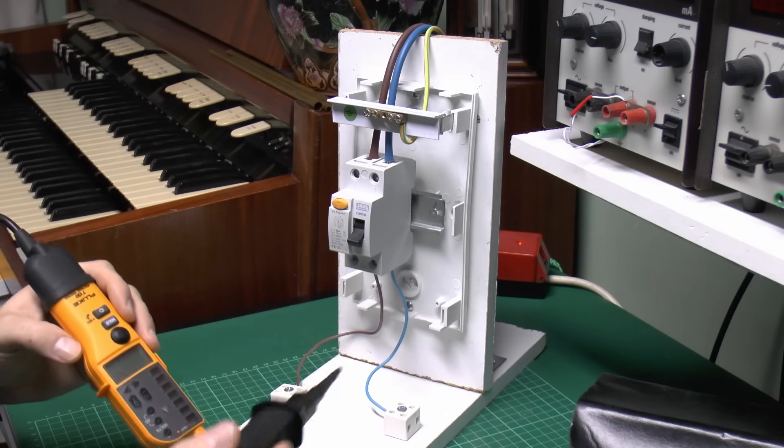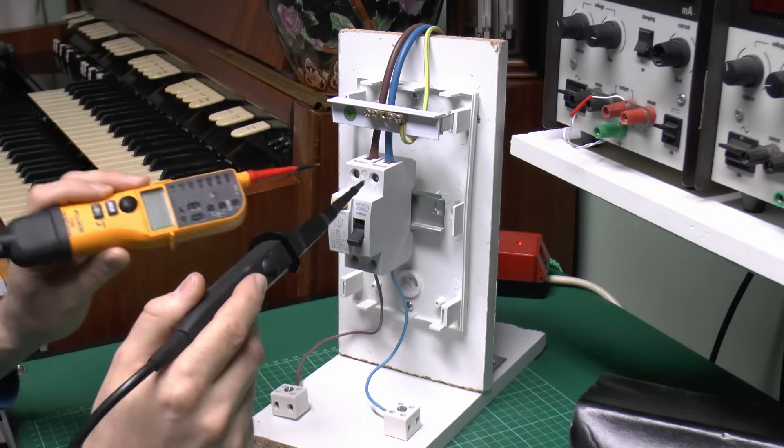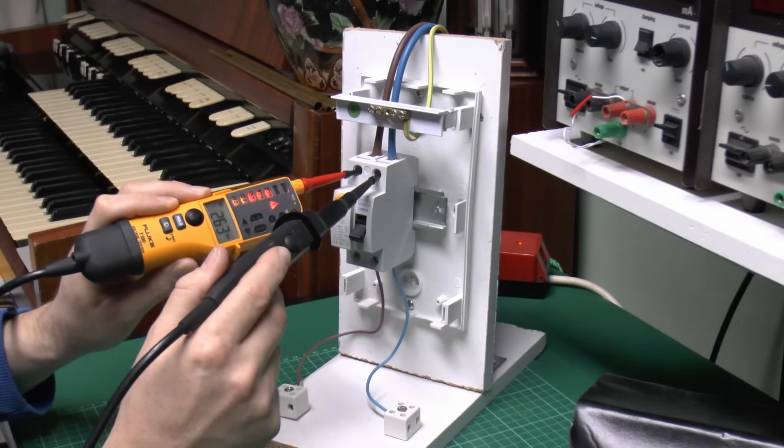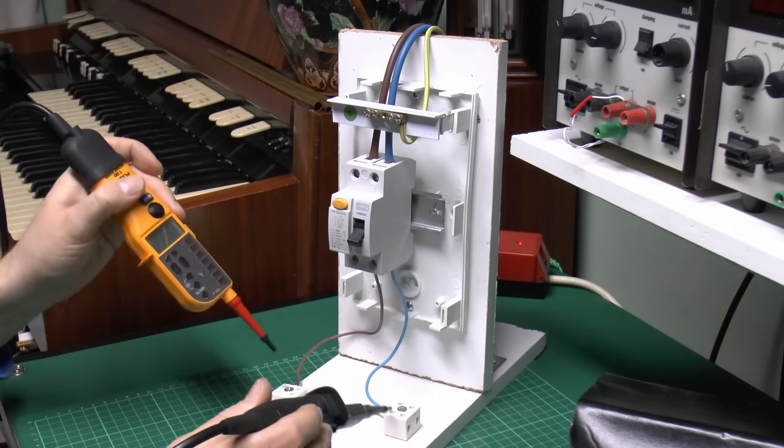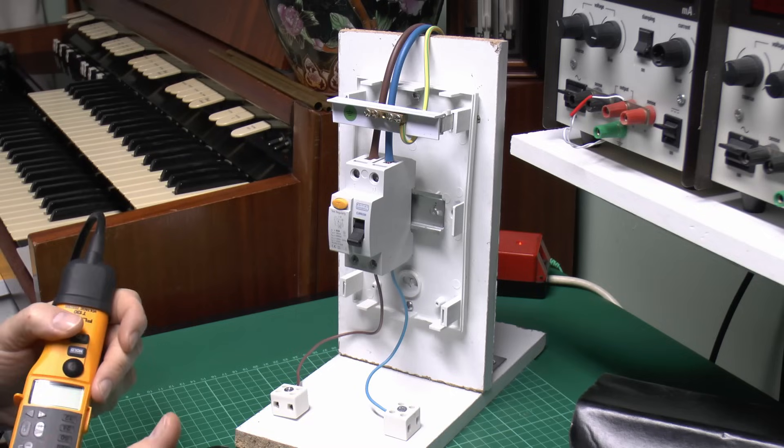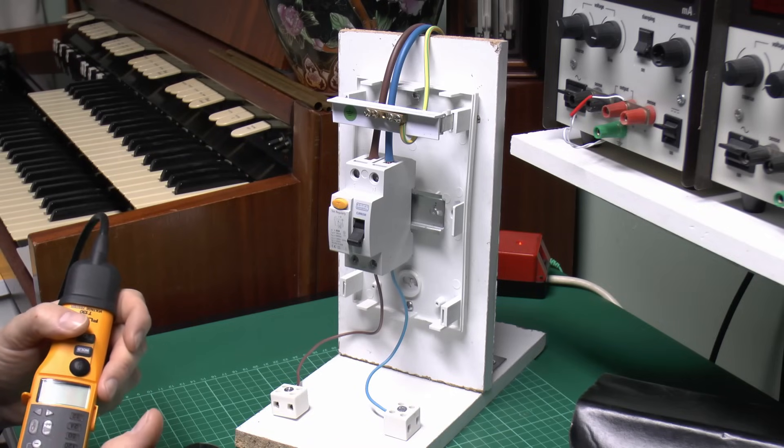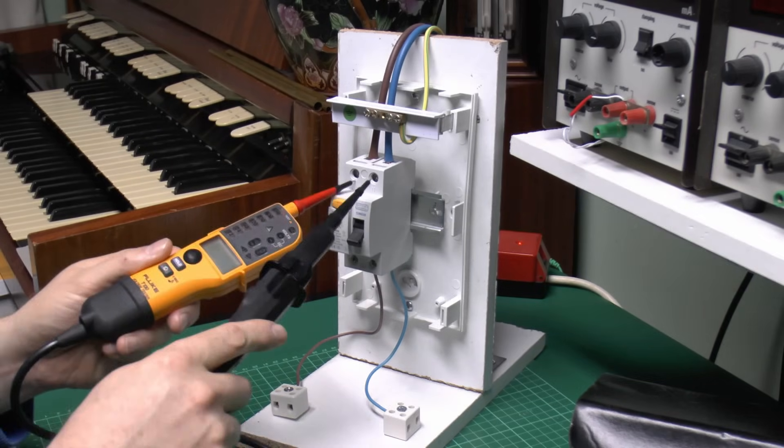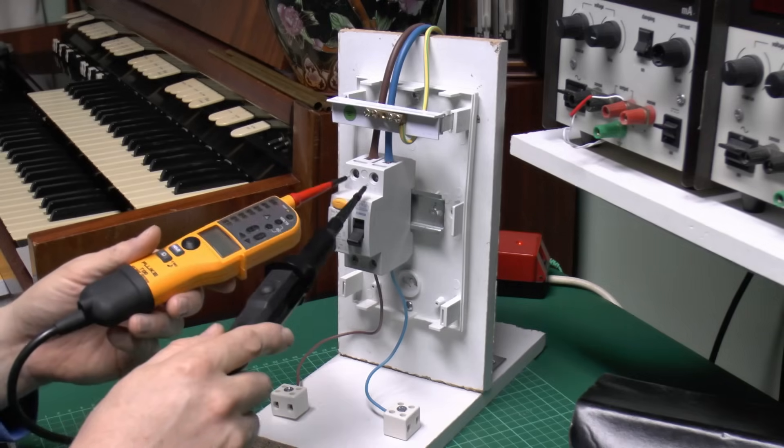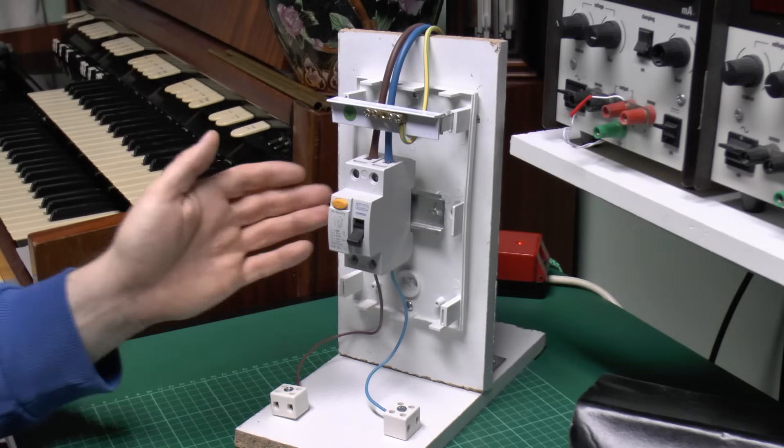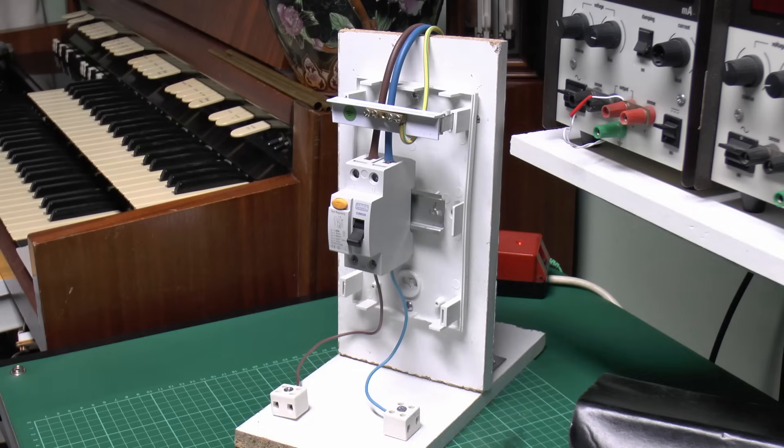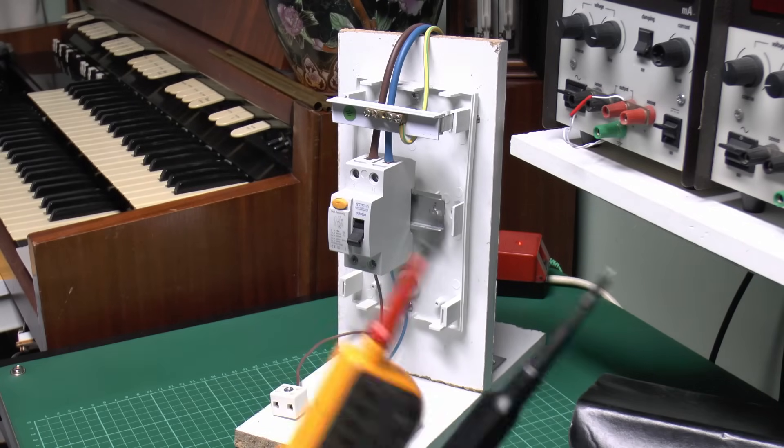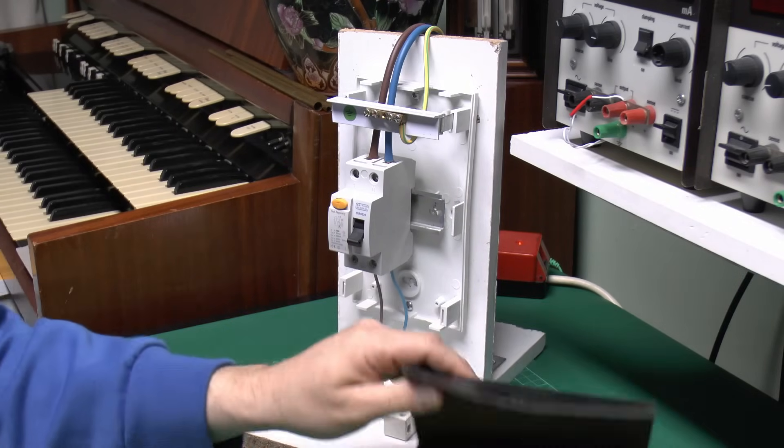But of course that's not the end of the story, because we still need to make sure that this is actually still working, because though it's fairly unlikely, there is a remote possibility that when it was switched off it's now broken. So we need to check again on a known supply. Now in this particular case, say this was a consumer unit, we've still got power at the incoming terminals here, so we could go in there, again just check that that's still working there. So no problems with that, so again check before and after, and then of course you have good confidence that the thing you were testing is actually disconnected. Now in circumstances like this where you've always got the sort of live terminals coming in on your consumer units or whatever, then of course it's easiest to go in there and check that those are still working. But there will be circumstances where this is not the case and you don't have a ready supply of the power to actually confirm that this thing is still working.